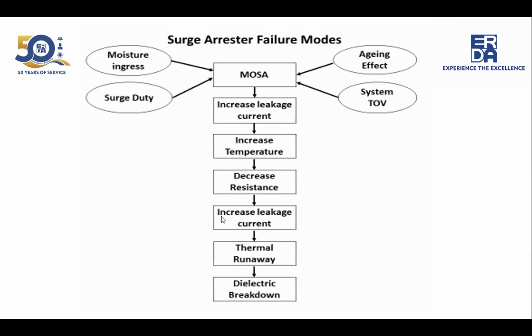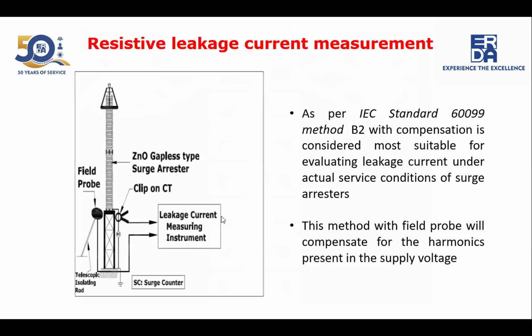And since the temperature is increasing, the resistance gets reduced, and as a result the current increases further. All this happens, and because of that the surge arrestor turns into thermal runaway, which is the basic reason for the failure of surge arresters. So if we want to safeguard the surge arrestor or the system, we should always avoid the thermal runaway condition. To avoid that, we need to check the healthiness of the surge arrestor at equal intervals. These are the techniques by which we monitor the healthiness of the surge arrestor.